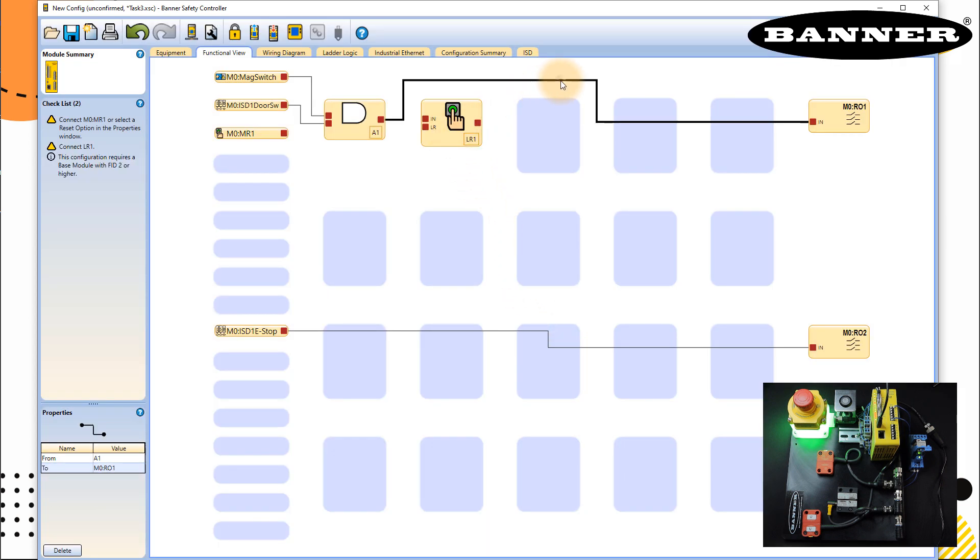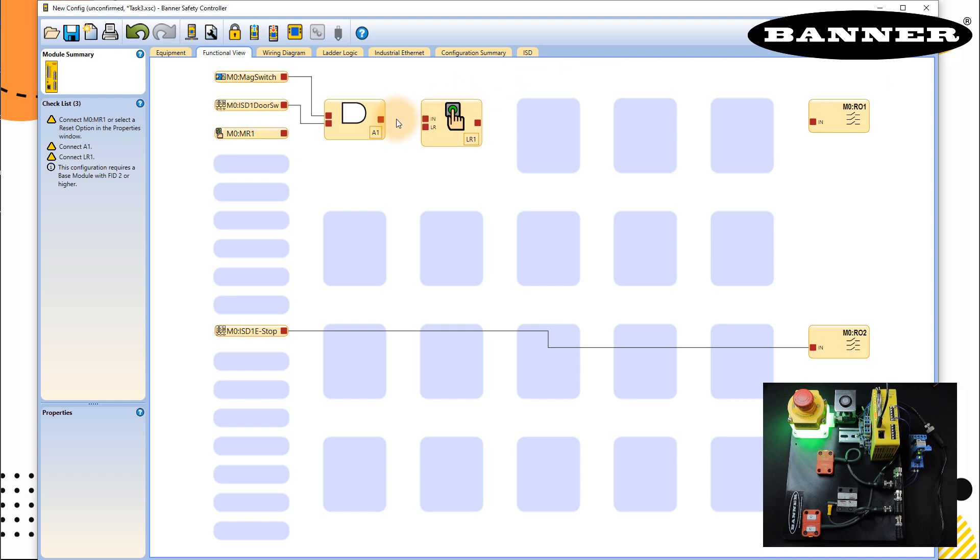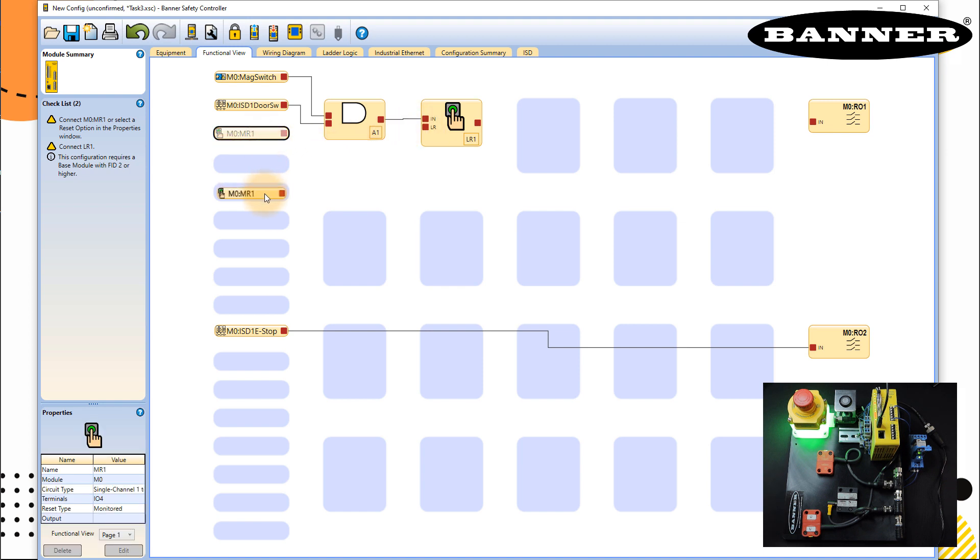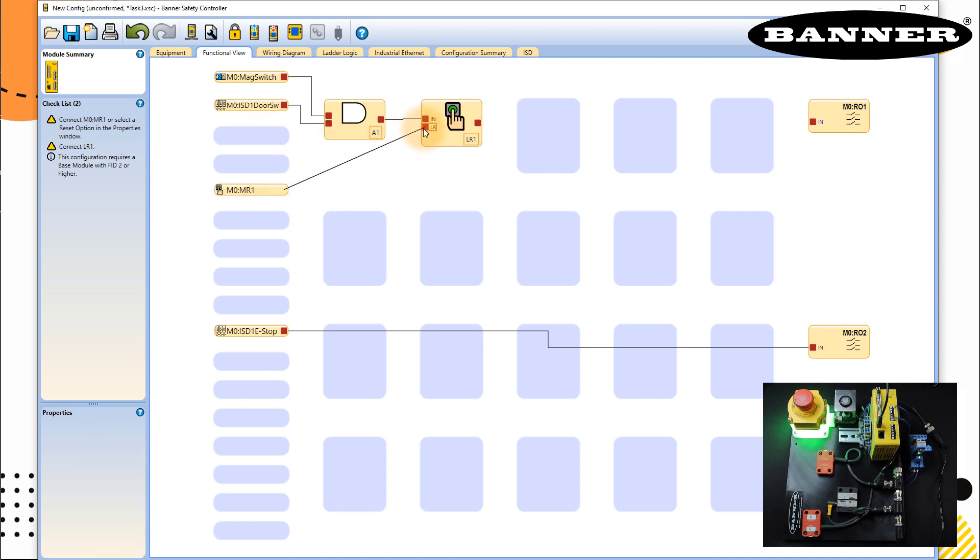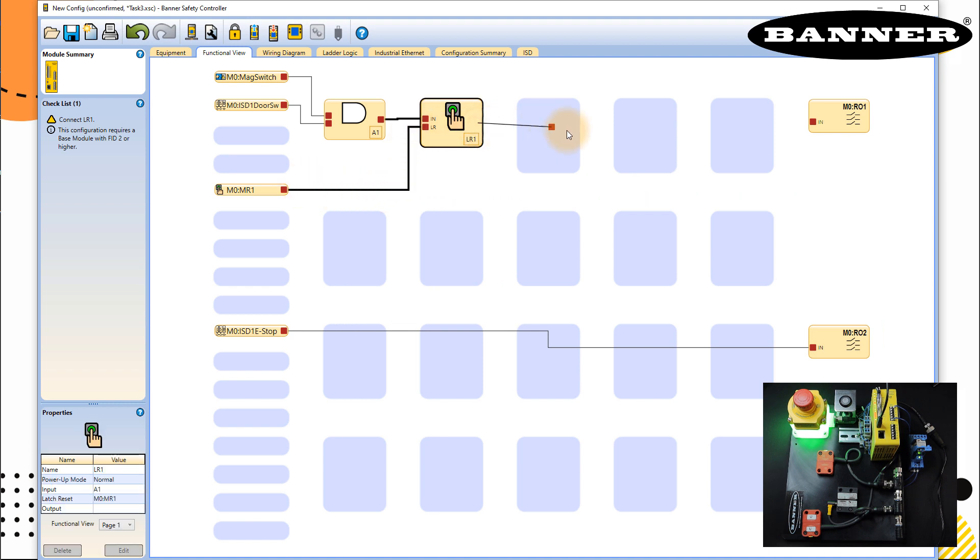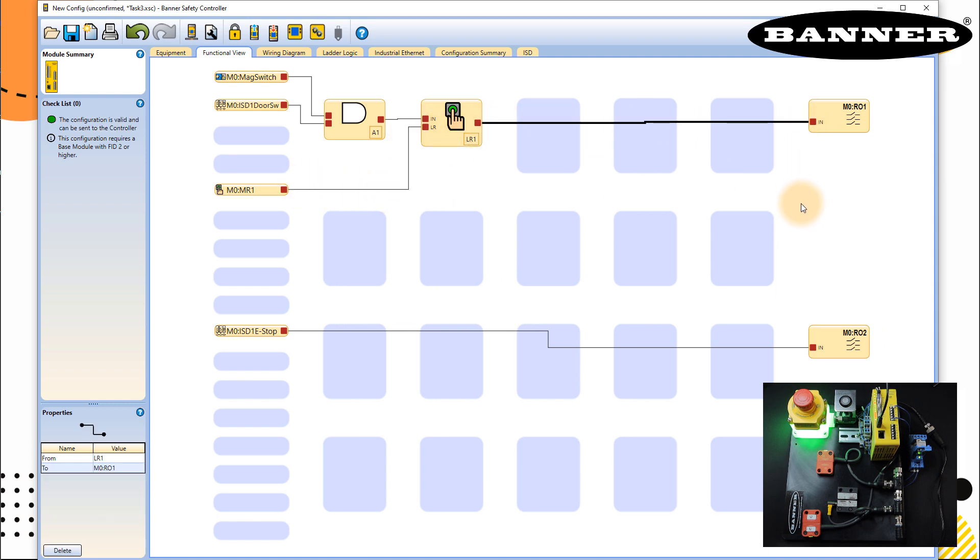This block is here. Now we can delete this connection and connect this output of this AND gate to the input. And this is our reset. So we can bring this reset down, connect it here. This is connected to my LR block. And then you can connect this directly to the input. So now this button will reset this LR block. Now what this LR block will do, this will latch the output. And this will also unlatch the output, I will show you in a while.